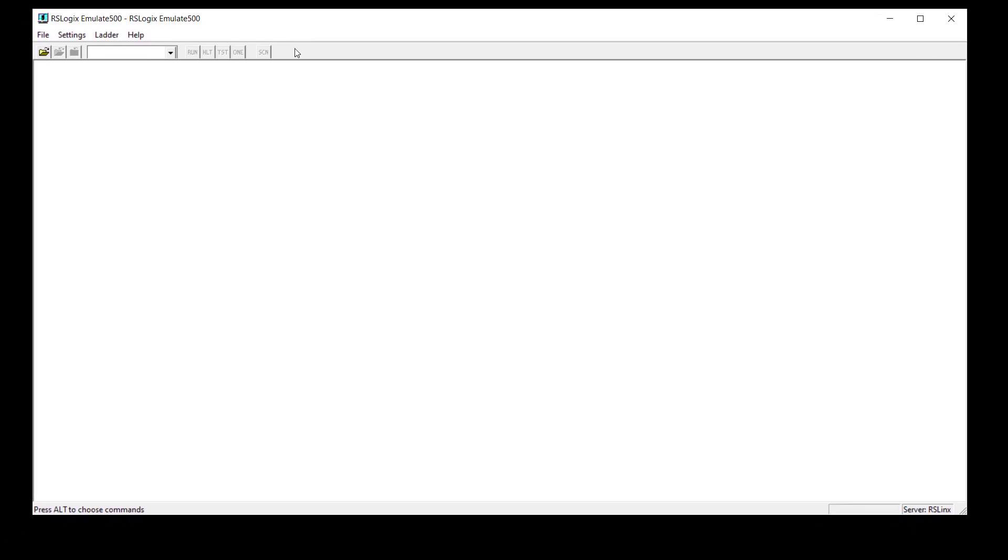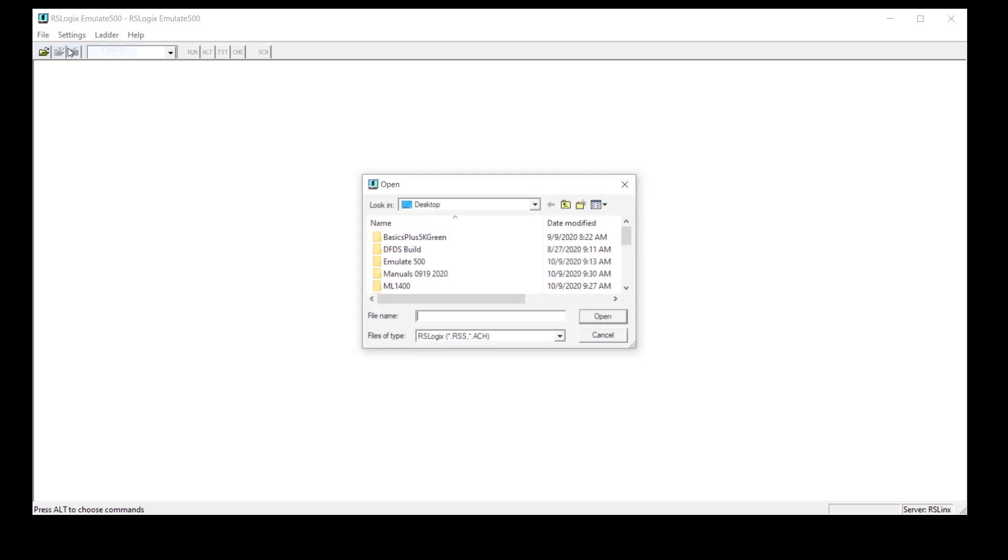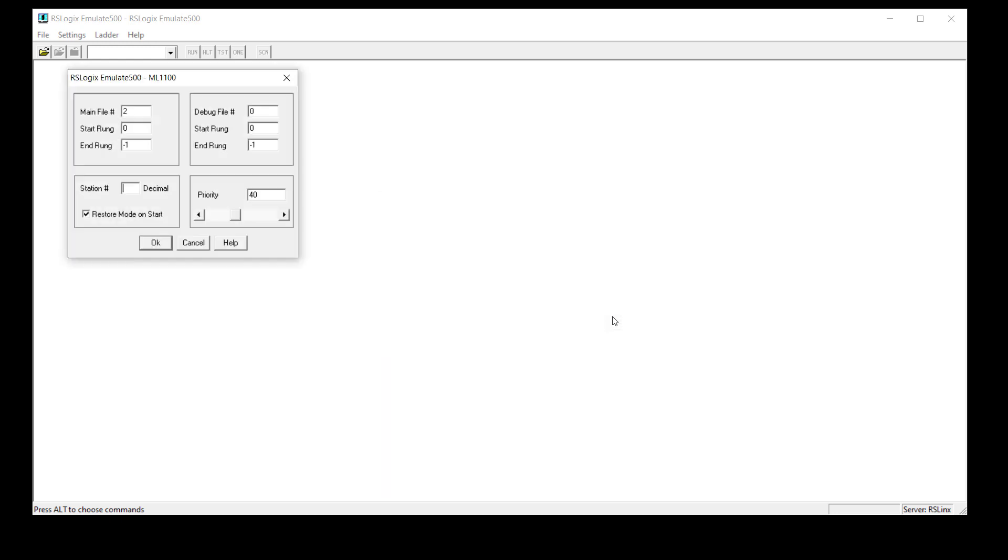We'll minimize this. And then we'll bring up, we'll open up the emulation. And this is an instance of the emulator, but it's an empty shell. So there's really nothing there other than we have set aside a chunk of RAM for the emulation. But there's no emulation there yet until we open a file. So you cannot download to this empty emulation because it's not there to find. There's no characteristics there. There's no personality. So we go find our program. MicroLogix 1100. We open it.